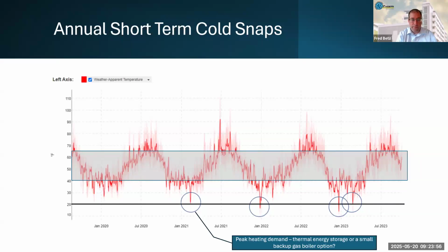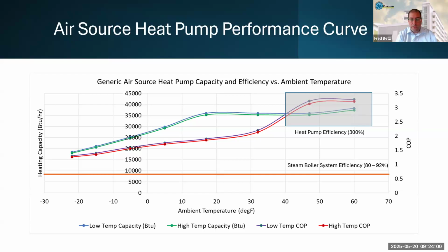So next slide, please. So one way in which that climate really impacts is on the electrification of heating. And so this is a generic air source heat pump capacity and efficiency chart versus ambient temperature. So x-axis is the ambient temperature, and you can see while that gray box there in the upper right is what is maybe often touted as the efficiency of heat pumps, so a COP of 3, and then there's their capacities and so on. The reality is that is a variable number, right? And so one of the challenges that is often surprising, and it has created this myth that heat pumps can't provide a sufficient capacity of heating, when in fact they can. You can see that it still has heating capacity down to -20.